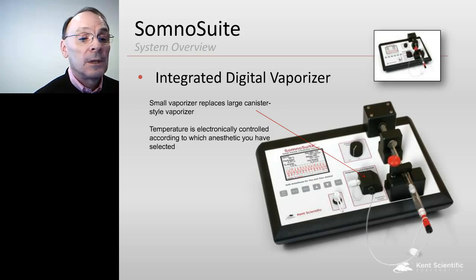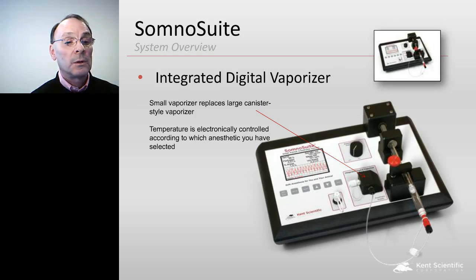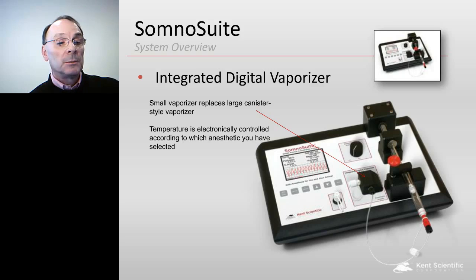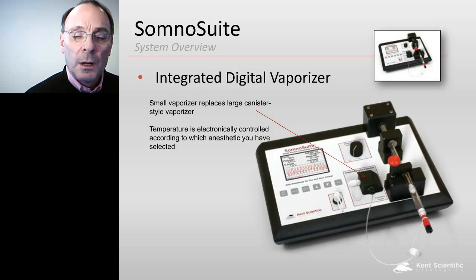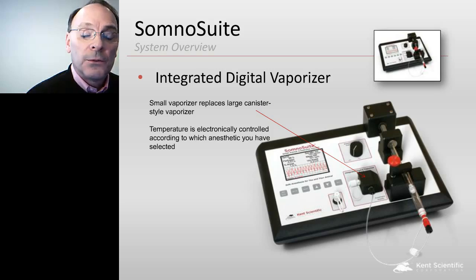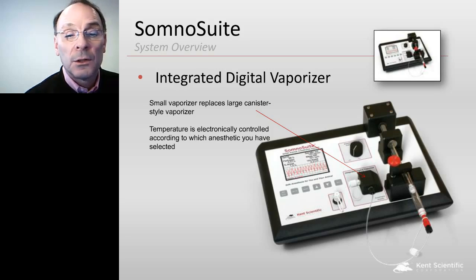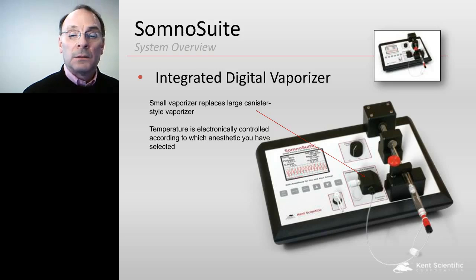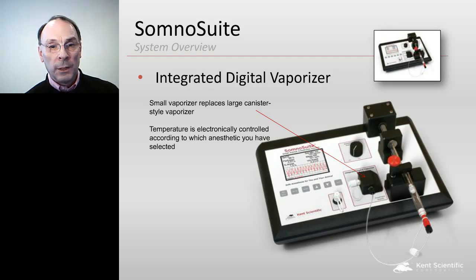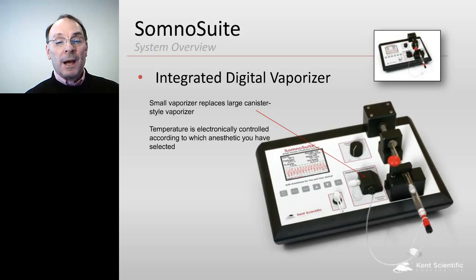What's the maximum length of time that the unit can be used for? Is it possible to refill the anesthetic in mid-stream? Well, for a mouse, typically you can run a good 4 hours on 2 mLs of isoflurane. If you're using sevoflurane, which takes a higher percentage, it would be less than that. But for isoflurane, about 0.5 mLs per hour. So if you put a 5 mL syringe in there, you could go almost 10 hours on it.